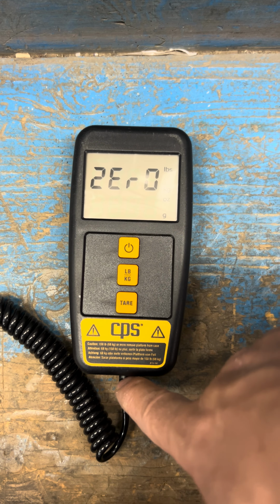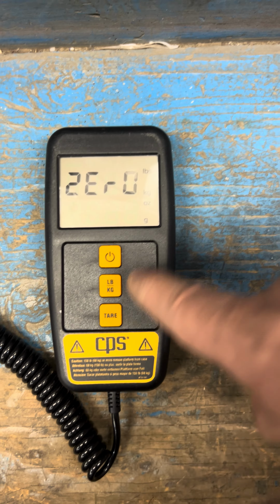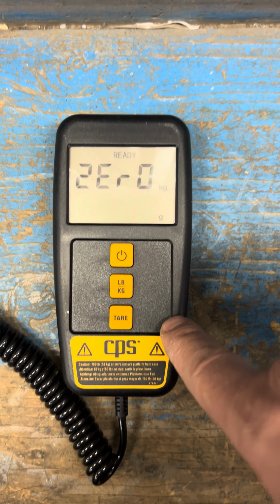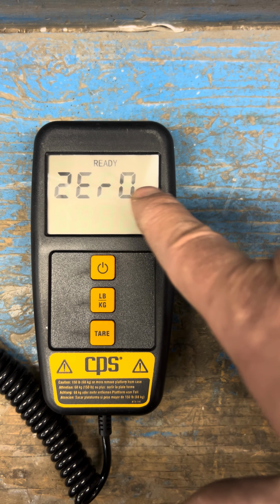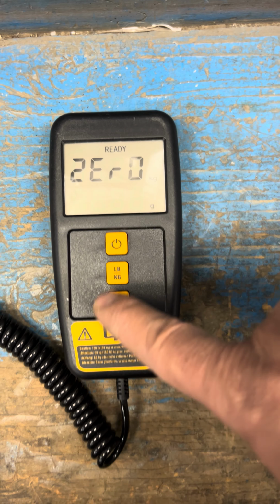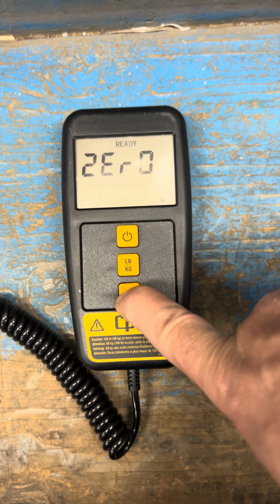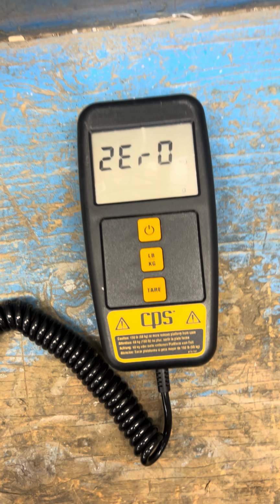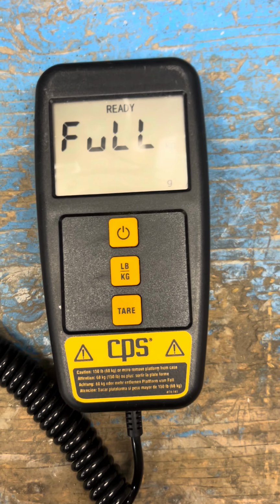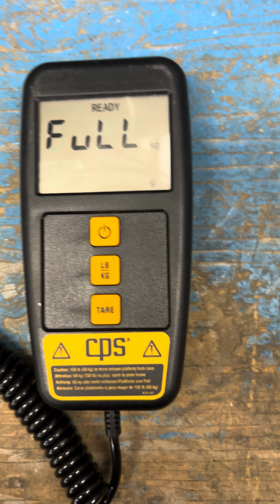Now it's asking us about zero calibration, but before that we need to choose units. So we press kgs, and now we have kgs units here, and it's ready for zero calibration. So we press the Tare button to calibrate zero now. Nothing on the platter. So now it's asking us about full capacity.